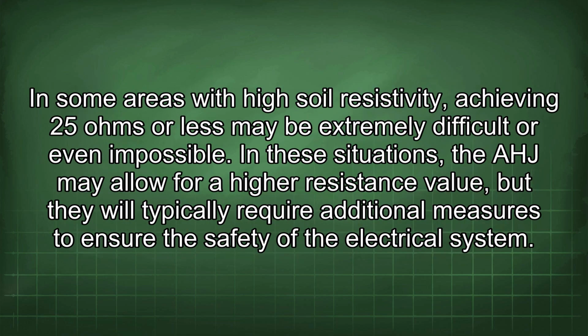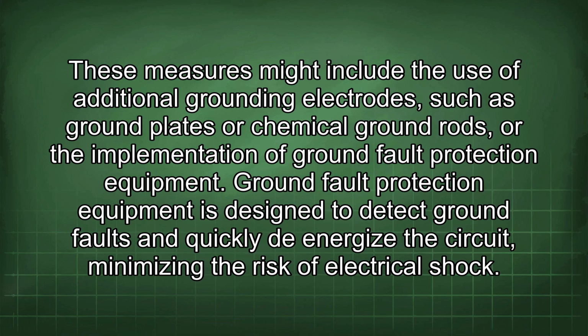In some areas with high soil resistivity, achieving 25 ohms or less may be extremely difficult or even impossible. In these situations, the AHJ may allow for a higher resistance value, but they will typically require additional measures to ensure the safety of the electrical system. These measures might include the use of additional grounding electrodes, such as ground plates or chemical ground rods, or the implementation of ground fault protection equipment.